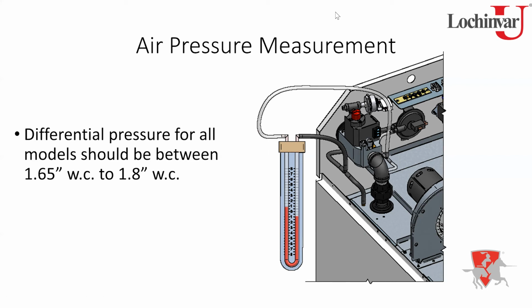Yeah. And here's one other piece of advice I want to give you. I don't remember if Charles said this or not. If you are the one doing this startup, or if you clean it and set this thing up, I want you to use a Sharpie and mark where you had that air shutter to give you the proper air differential to where it ran fine. Because if you come back and someone came behind you and pulled that thing open to basically Band-Aid a dirty burner, a blockage, a venting issue, or something of that sort, you'll know.